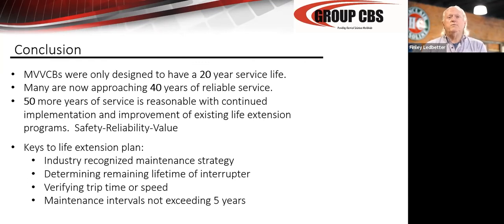Keep the breakers well-maintained, well-lubricated, well-tested, and that solves most of these other problems. Verify your trip times occasionally. Put that into your specifications where you know the health of the mechanism. The mechanism is the most important thing, and lubrication is key there. Maintenance intervals, I'm going to recommend not exceeding 5 years before you do this testing. I know some people do. It's a bad idea, okay?